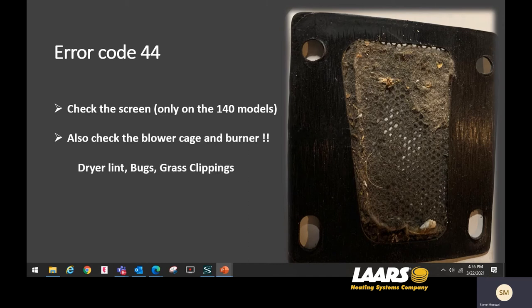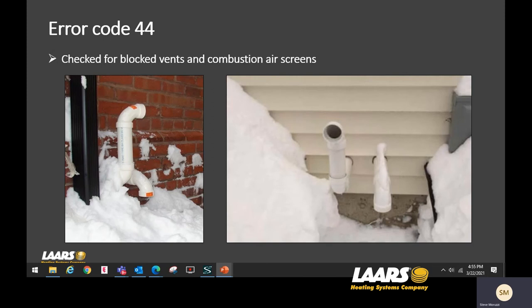PVC shavings are also very common, especially on startup — you can hear them getting drawn through the vent into the mixing station and sucked into the blower, eventually into the burner. For error code 44, check for blockage and snow. Vents are supposed to be 12 inches above the anticipated snow level. In New England, if anticipated snow level is 2 to 3 feet, the exhaust and combustion air vent should be a foot above that — in most cases they are not, so in snowstorms these will plug up.